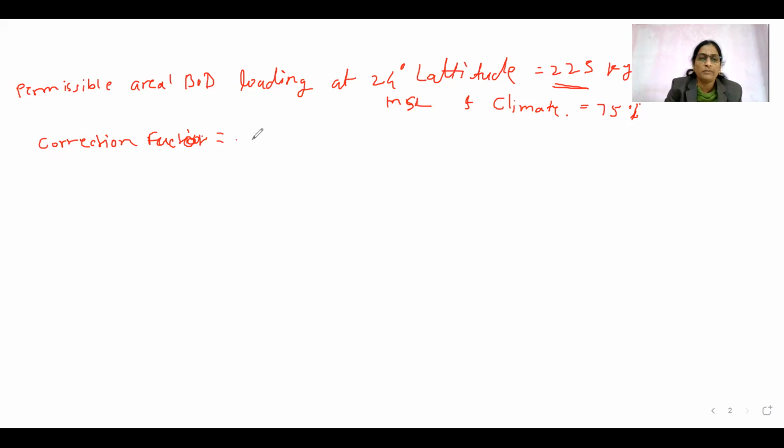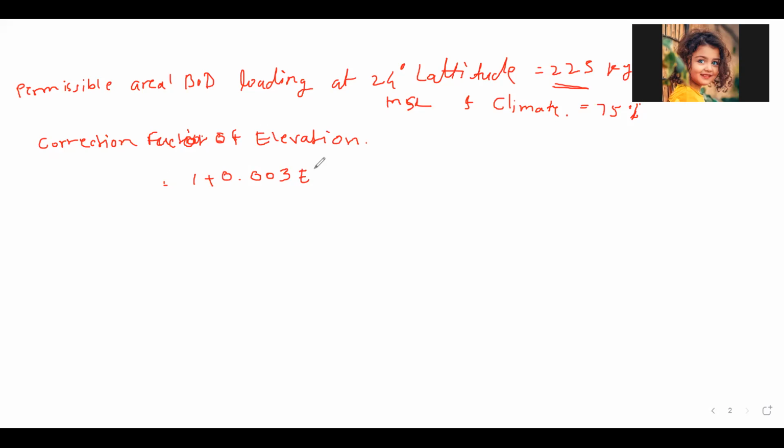What is the formula to apply the correction factor of elevation? Please tell me the formula. 1 plus 0.003 EL.